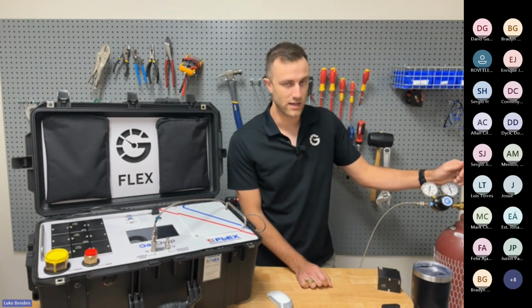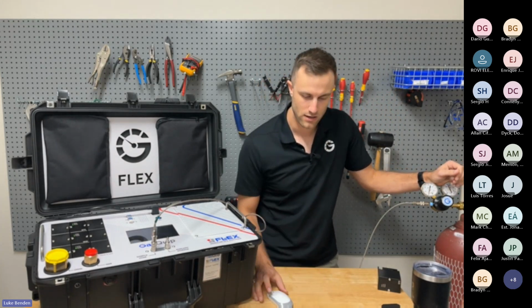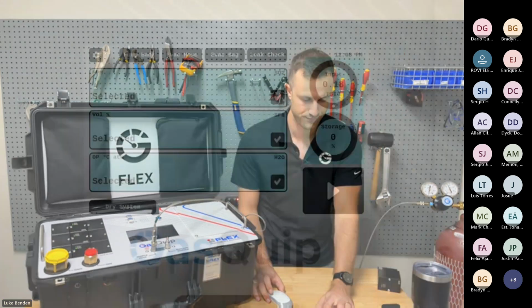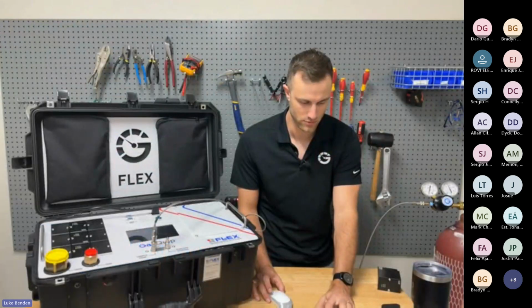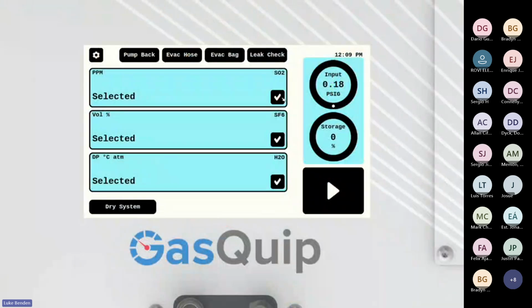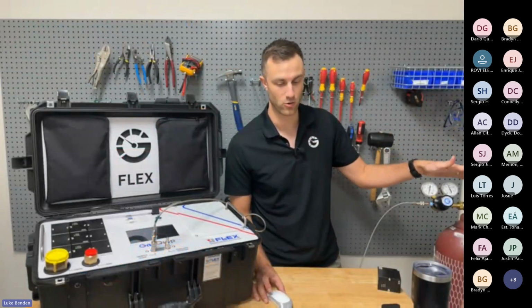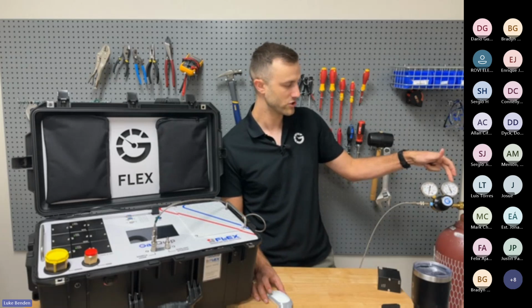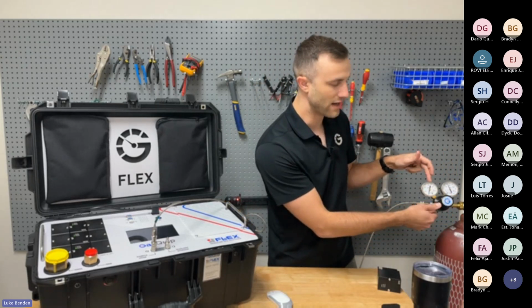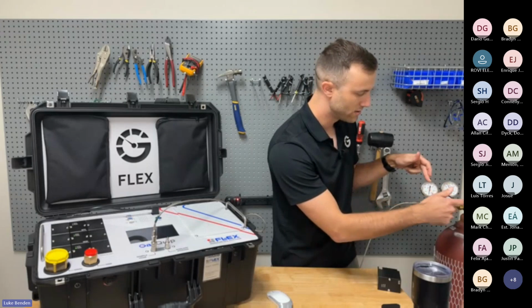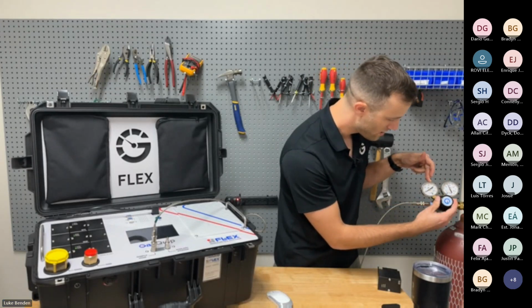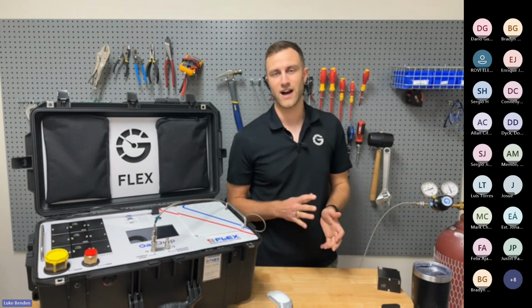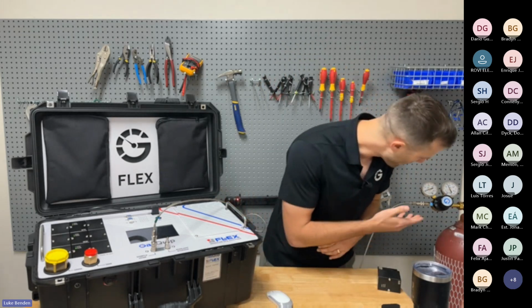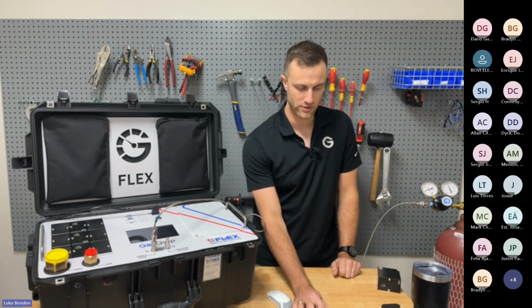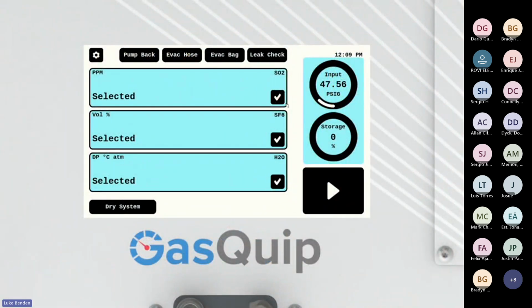Now what we'll do is introduce gas into the line. And if you look here on the analyzer, the input pressure should jump up to whatever pressure we set here on our regulator. So we have our input pressure here on this gauge, and we'll increase the pressure going on the output by turning the knob clockwise like so. You need the pressure to be anywhere from 5 to 145 PSI. So we'll put it on 50, call that good. So if we go back to our analyzer, we got 47.56. Now we can run a test.